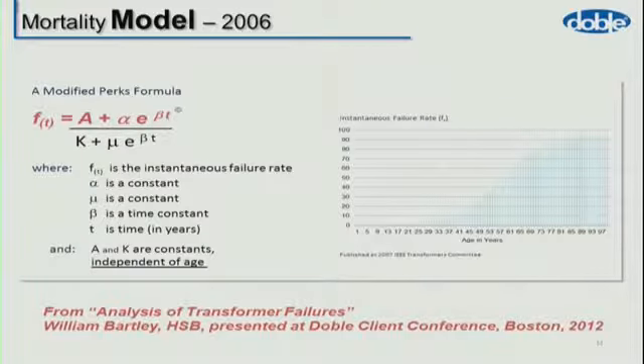Two things: what are the accuracy and precision? What are the error bars on those measurements? They're huge, so we have to be very careful about using these things. But it does say, based on his information, that about half your transformers should have failed by the time they're 40 years old. In my experience with Doble, having looked at thousands of failures around the world, that's not the case.